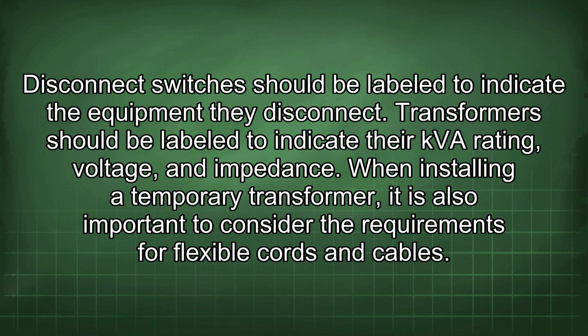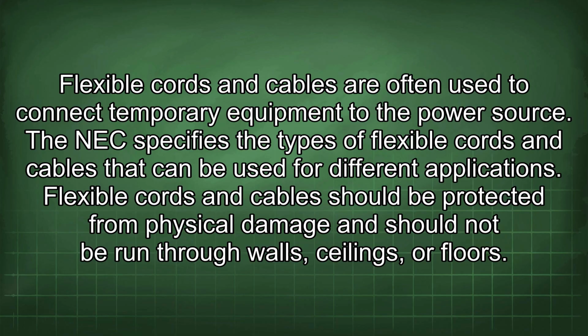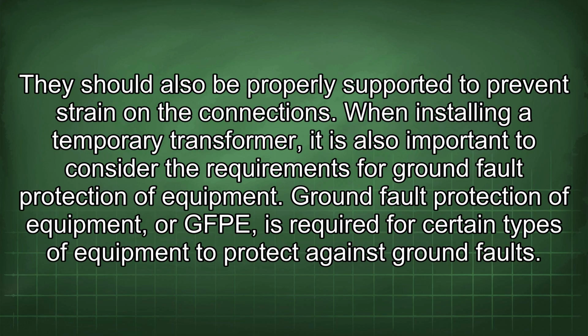When installing a temporary transformer, it is also important to consider the requirements for flexible cords and cables. Flexible cords and cables are often used to connect temporary equipment to the power source. The NEC specifies the types of flexible cords and cables that can be used for different applications. Flexible cords and cables should be protected from physical damage and should not be run through walls, ceilings, or floors. They should also be properly supported to prevent strain on the connections.